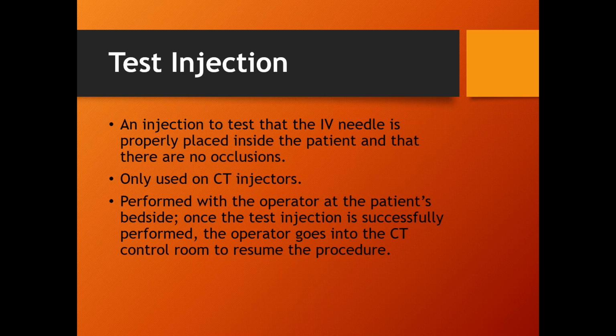Your test injection has to be first phase, all right? There's no point in doing three phases of injections and then saying, maybe we should see if we actually hit the vein. So your test injection is always phase 1, and it's always followed by a pause. So when the test injection is over, they don't have to hit the pause button and go back into the control room and finish off the rest of the injection.